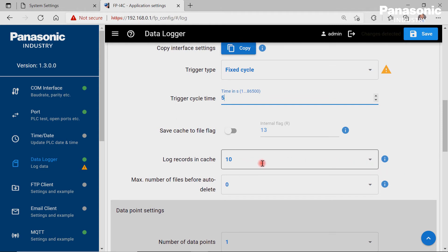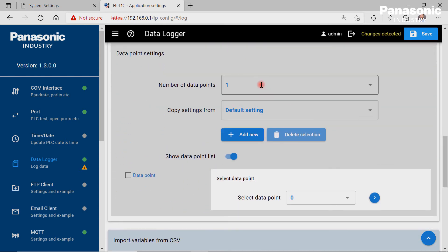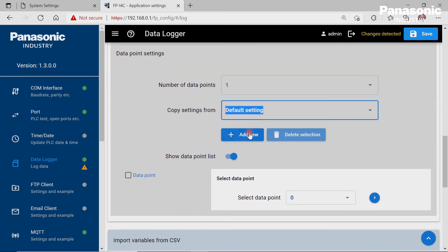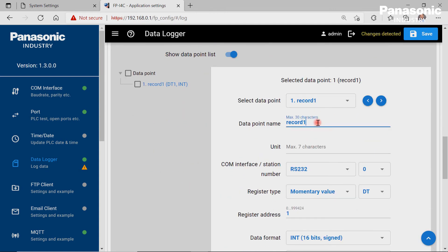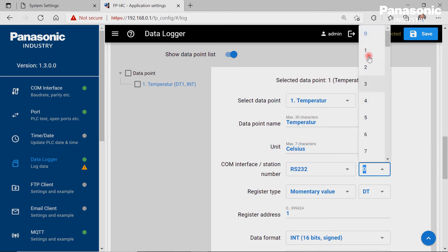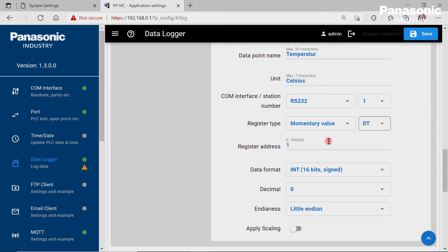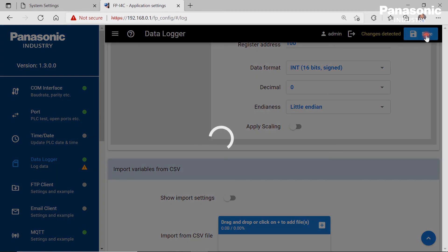After 10 values have been logged, they shall be written into the log file Station 1. The next step is to define the data points we want to log in the log file. We click Add New, set the data point name and unit. The COM interface is again the RS232 connection and the station number is 1. After the configuration settings are done, we save it to activate the new settings.